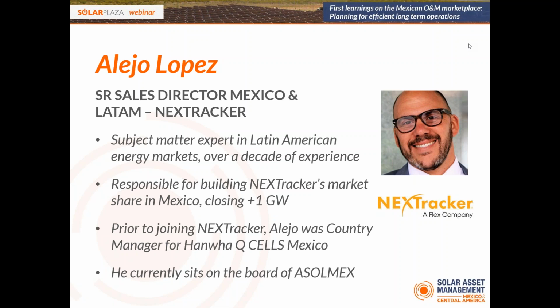The next level, and this is the beauty of the decentralized structure - that's one aspect, the risk mitigation. The second is the granularity it gives you in terms of information and control. So you have information for a string inverter at a string level, and for a tracker at a mechanical level - for example, for us, 1500 volt, 3 strings. You can get all the way to that point to narrow down a problem. Problems happen all the time, like Hector says - it's one thing or another.